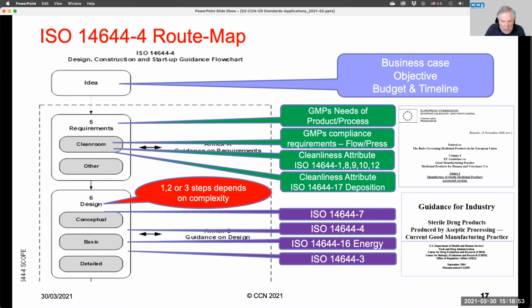Part 3 includes the testing. So I would say absolutely you have to consider how and ensure that the design is testable. One of the most common things is finding out that nobody thought about how to do the in situ leak test of the HEPA filters in the design phase, and there were no convenient injection points. And it turned into a nightmare during the startup and even more of a challenge to the user during the operational routine testing and certification of the clean room. So part 3 has a whole lot of elements that should be incorporated in the design. And then, of course, I'd also have GMP qualification aspects. So during the design, I'm going to involve verification through design qualification, for example, maybe at more than one stage in the design.